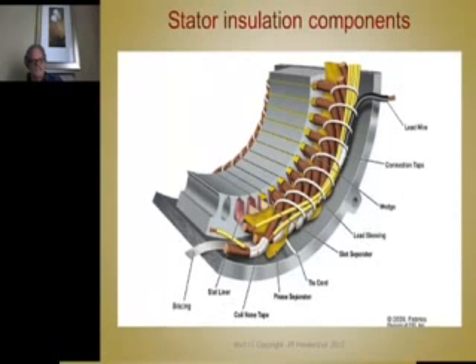Okay, that is sleeving over the magnet wire, but that could be hookup wire, or heavier gauge lead wire, soldered and crimped and attached to the magnet wire as well. Oh, there, that shows the lead wire. So this is the pigtail of magnet wire, several strands per turn. See it there. And then somewhere that is soldered or crimped to a lead wire, which is multi-strand also, but heavier in gauge. And so there's the joint with tape around it, where the magnet wire was attached to the lead wire. And here are the phase separators I spoke about.